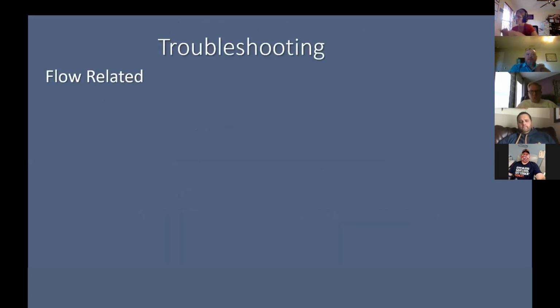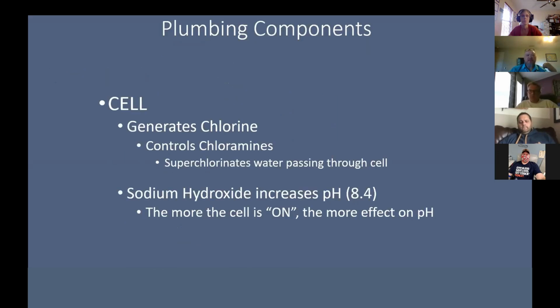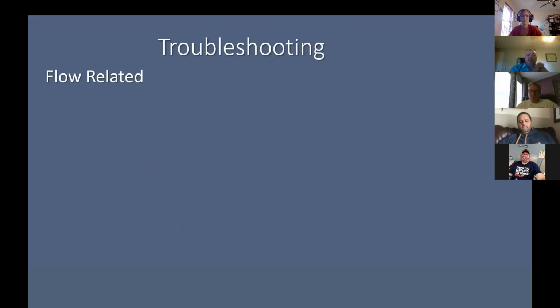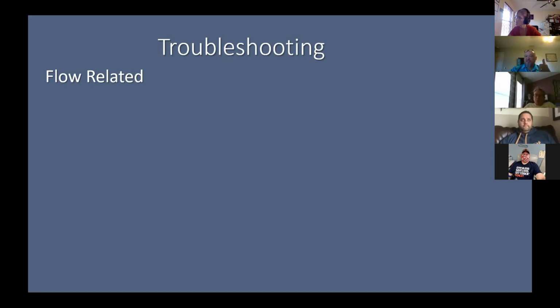All right, so when we're troubleshooting related to flow, one of the things we have to be aware of is that if there's insufficient flow going to the cell, remember we're making chlorine, we're making hydrogen gas, we're making oxygen, right? If there's insufficient flow going through the cell to evacuate those gases being generated, the hydrogen gas can accumulate, and accumulation of hydrogen gas can cause a combustive reaction. So that's what we want to avoid. And that's a primary reason that there's a flow switch in every salt system, all right?